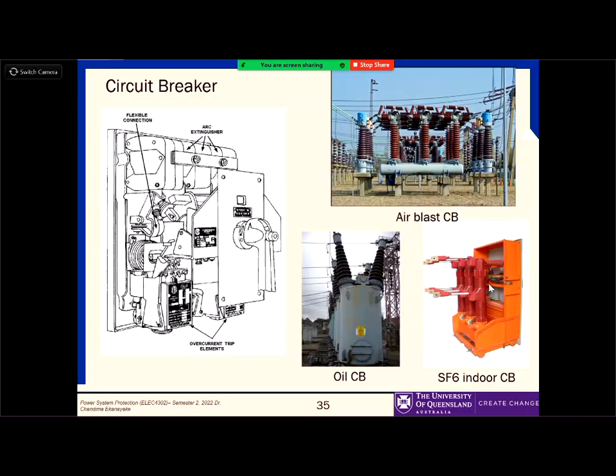When you learn these circuits and associated components, industries usually refer to circuit symbols rather than names. It's not given as 'this is an overcurrent relay'—instead, for instantaneous current relay, they use number 50. Number 51 is the time delay relay, and 51N is the neutral connected relay. So those symbols exist, and 52 is the given code for a circuit breaker. You will find all these in many documentations.